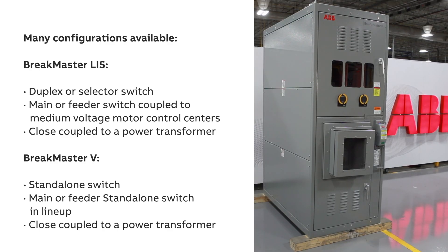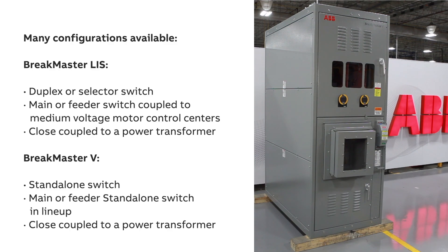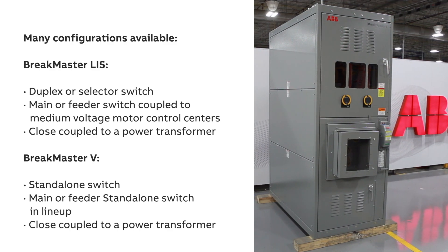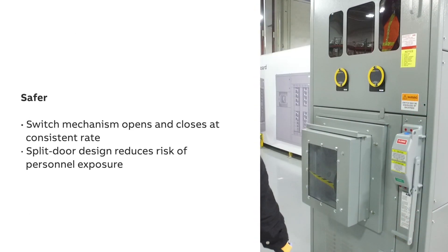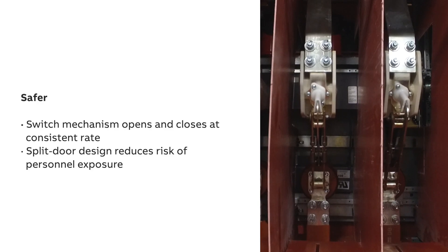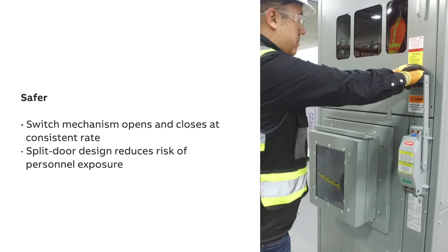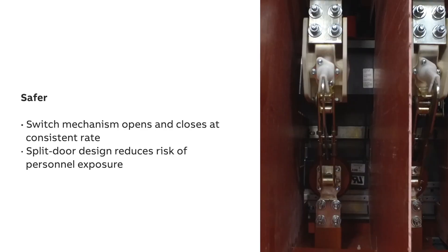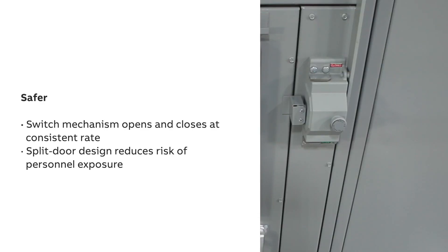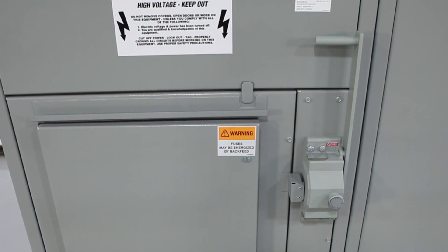BreakMaster V can be configured as a standalone switch, as a main or feeder switch in a lineup, or close-coupled to a power transformer. The switch mechanism in both BreakMaster LIS and BreakMaster V is a quick make, quick break design that opens and closes the switch at a consistent rate regardless of the speed at which the operating handle is engaged.